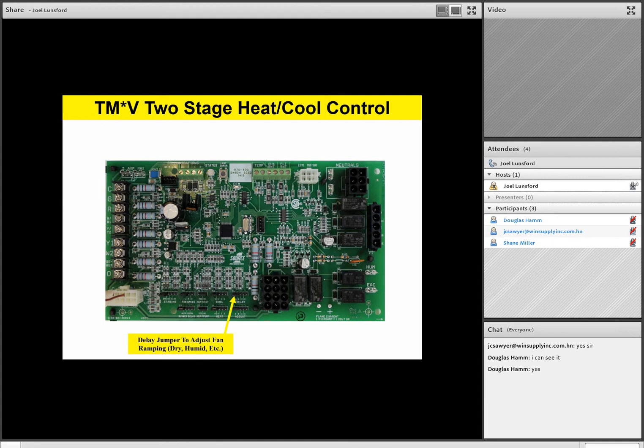A is what we call normal. That would be someplace like maybe South Dakota, or someplace that's kind of dry in the wintertime and cold, but you don't have to worry about having a lot of humidity in the cooling mode. So A is normal. B is humid, and that would be for humid environments like Mobile, Alabama, the Mississippi Gulf Coast, and so on. And that B is for humid profile. C is for dry. For instance, out in Arizona or southern Colorado, it's a dry area out there, New Mexico and Arizona and so on. And D is temperate, maybe Memphis, Tennessee, or in the middle of the country.